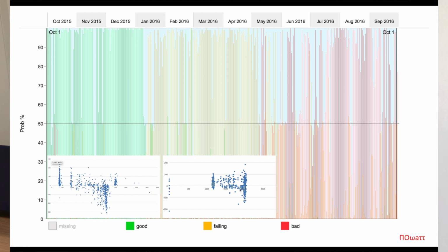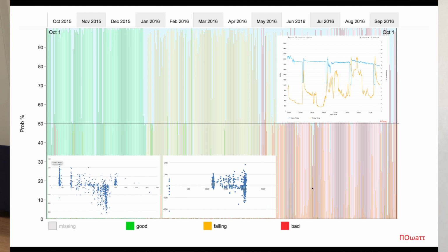But if we look at the second order pattern, see how different it is. So immediately, the AI says, this is a different pattern, and this pattern I relate to failing. I know if it keeps on like that, if it keeps on with the actual heater on the whole time, the compressor's going to fail.